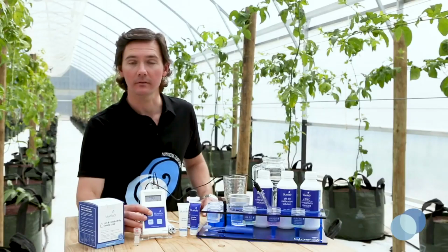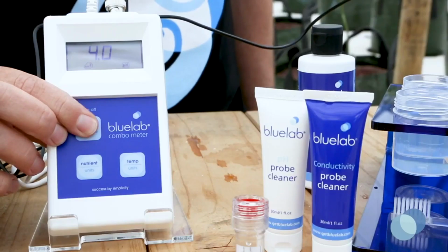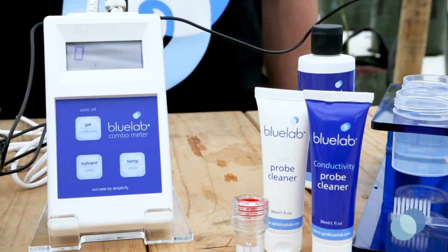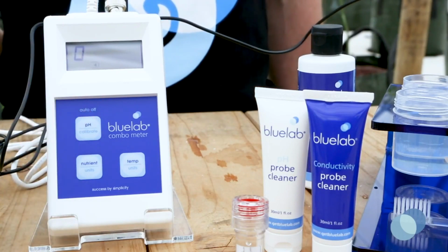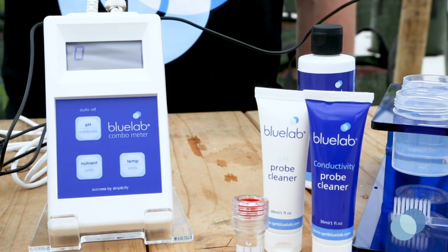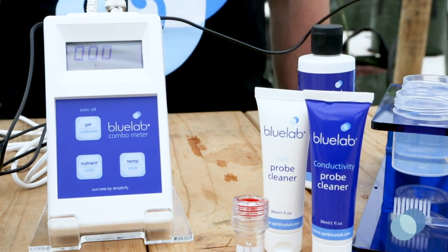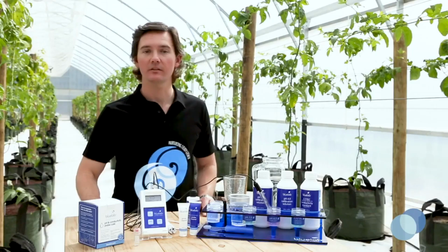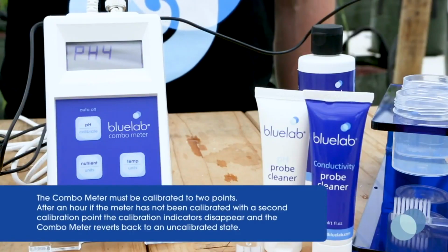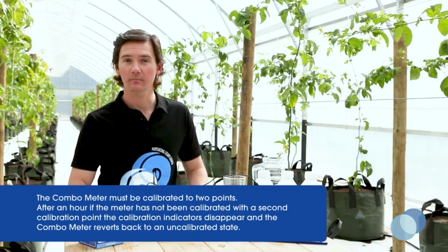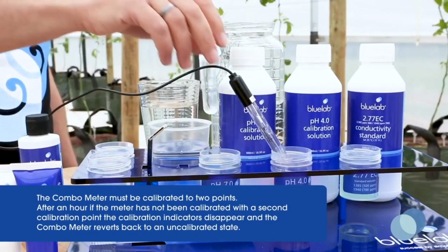Press and hold the Calibrate button until CAL displays on the combo meter screen, and then release your finger. You'll see a series of flashing symbols again letting you know the pH 4 calibration is taking place. When calibration is complete, you'll see the pH 4 calibration indicator appear on the display. The calibration indicators will be on the display until it's time to calibrate again.